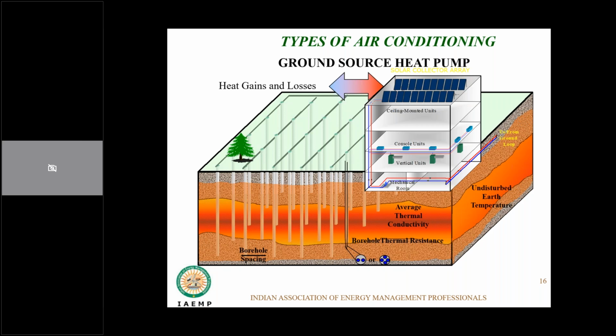And again, it works on the same philosophy that the earth below 6 meters, the undisturbed earth temperature remains steady, and wherein you can reject this heat out. But of course, you need to have multiple such boreholes and bury this pipe down, because over a period of time, you will find that the surrounding temperature of these boreholes will increase, and it will not be as effective. That is why, normally if I have to do it, we add almost 3 times more boreholes than a general requirement. This is just to make it effective for a long period of time.